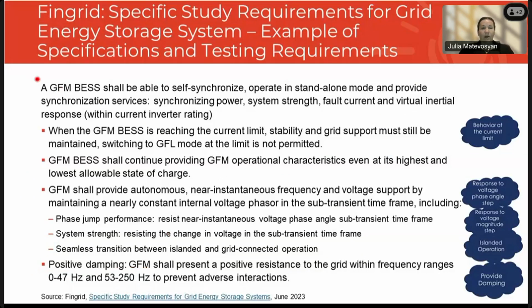Thank you. All right, so now jumping to Fingrid. Fingrid is a mix of functional specifications and testing requirements all in one document. I think it's an interesting case, because of the way they introduce the specifications, it's more for specific cases where inverter-based resources, battery storage inverter-based resources, would like to build in weak grid areas. So they are saying in these areas, inverter-based resources cannot be built anymore because of stability limits. But if it's a grid forming resource that complies with these requirements, then they can build in this area. So that's how it's being implemented right now.